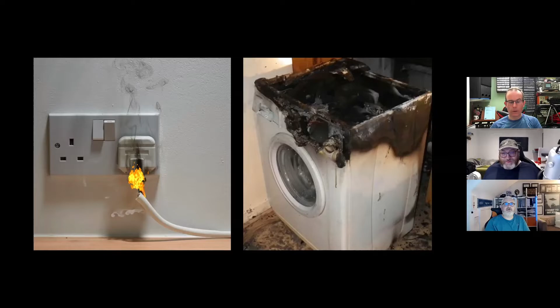It's now a shall, everybody, for single-phase AC final circuits supplying socket outlets and fixed current-using equipment not exceeding 32 amps. So 40 amp showers, forget it.